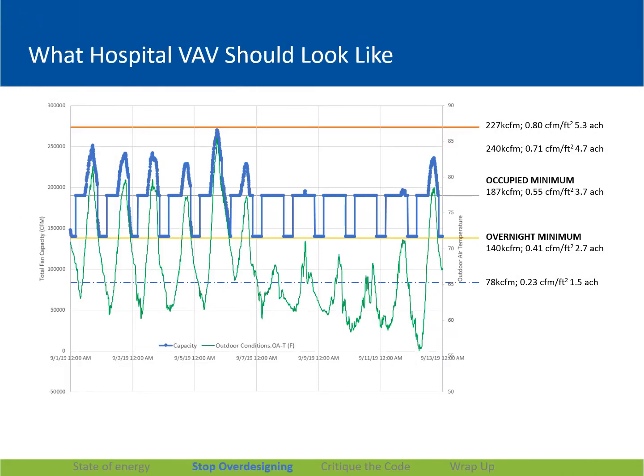So this is what VAV should look like. When it's warm outside, we should be seeing our peak air. But when there's mild temperatures during the day, we should be riding down at that daytime code minimum, and every night we should be seeing a solid drop off in our air quantity. The point of this slide is to stop blaming the code.